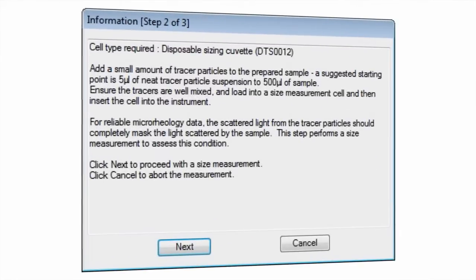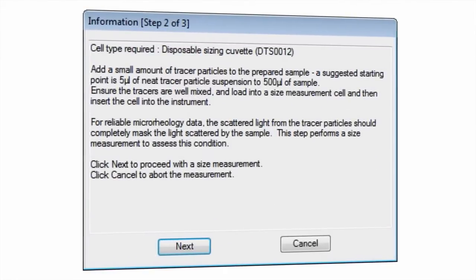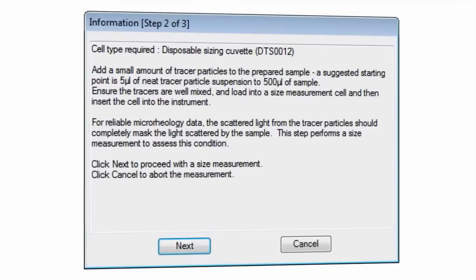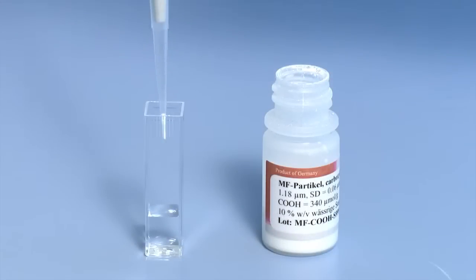These conditions are assessed by using a DLS pre-measurement step to compare the intensity particle size distribution peak from the sample against the intensity particle size distribution peak following addition of tracer particles to the sample.